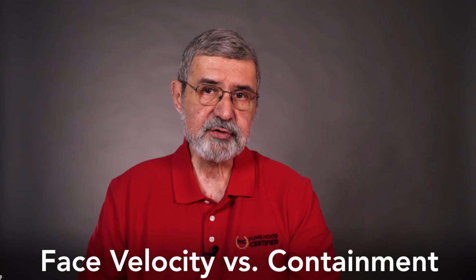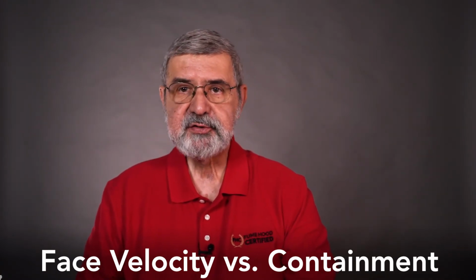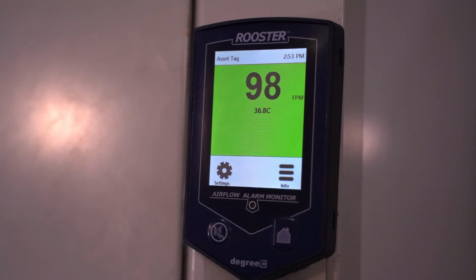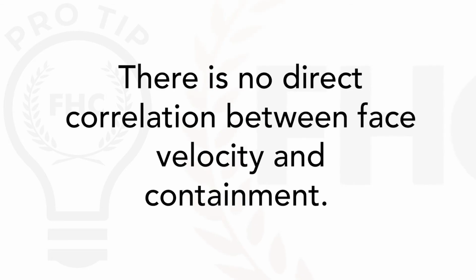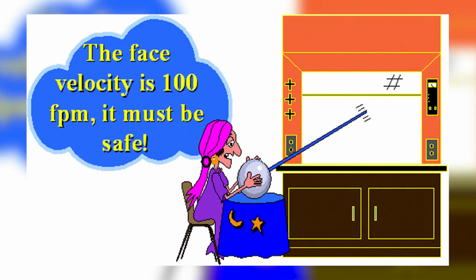Face velocity versus containment. There's a major misconception that if the face velocity shown on the hood alarm reads 100 feet per minute, then the hood must be working. But there is no direct correlation between face velocity and containment. Let me repeat that statement. There is no direct correlation between face velocity and containment. Just because the fume hood has 100 feet per minute face velocity does not mean it's working safely. In fact, when doing ASHRAE 110 testing, over half the hoods that failed containment testing had the specified face velocity.